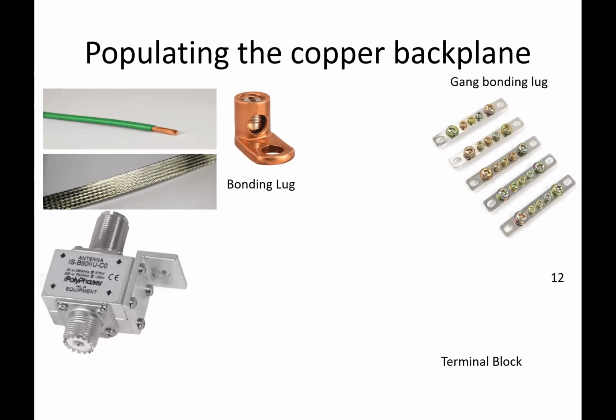But basically you're going to use bonding lugs to connect those wires to your backplane. The bonding lug is just a method of attaching a terminal to the backplane via a fastener. In the upper left corner, you'll see a copper bonding lug. It's got a set screw. You loosen the set screw, put your copper wires in there and crank down on that set screw, and it makes a mechanical bond between your backplane and the wire.